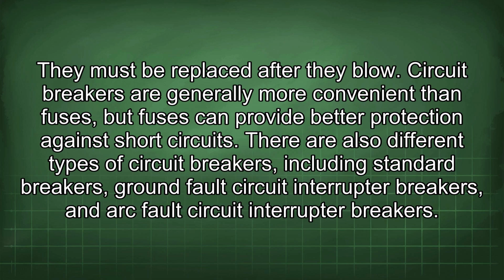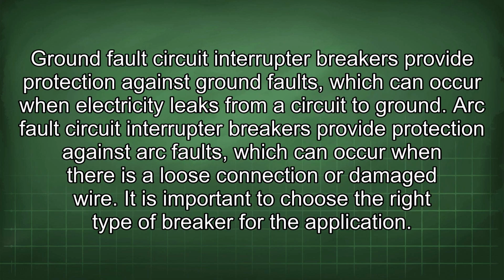There are also different types of circuit breakers, including standard breakers, ground fault circuit interrupter breakers, and arc fault circuit interrupter breakers. Ground fault circuit interrupter breakers provide protection against ground faults, which can occur when electricity leaks from a circuit to ground. Arc fault circuit interrupter breakers provide protection against arc faults, which can occur when there is a loose connection or damaged wire. It is important to choose the right type of breaker for the application.